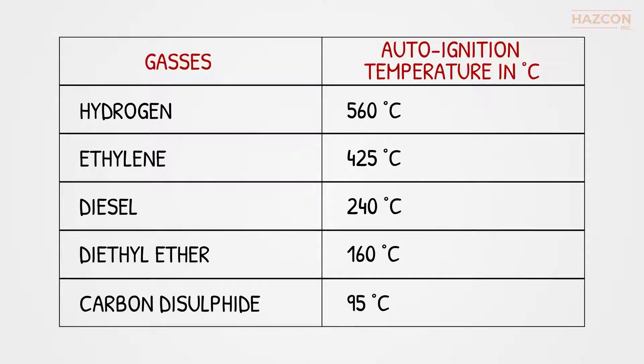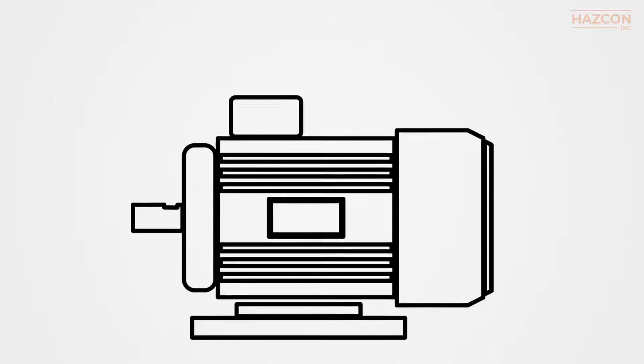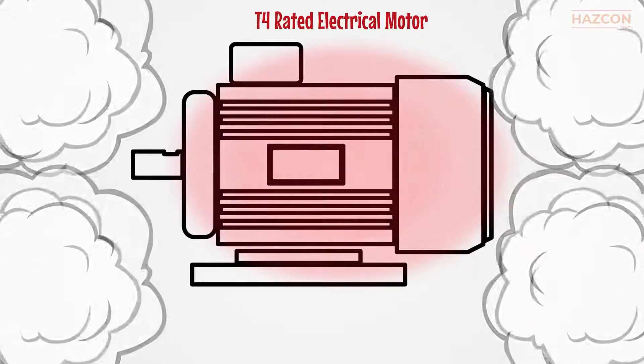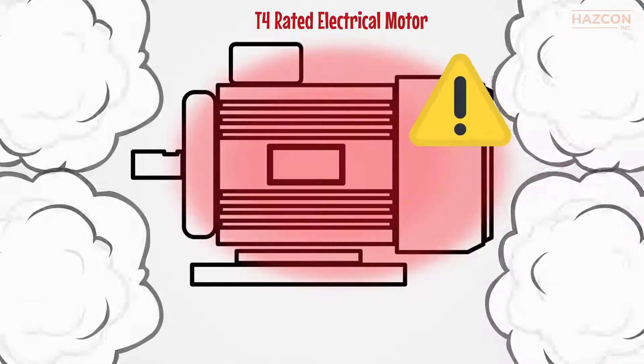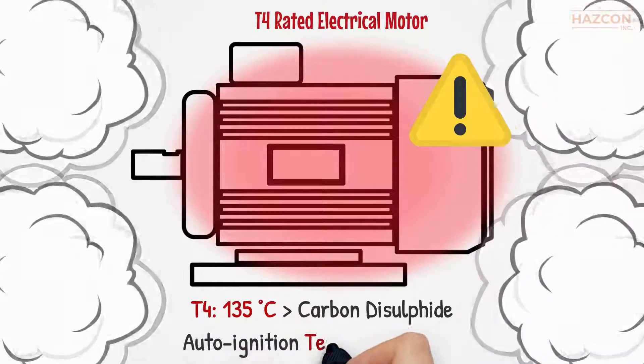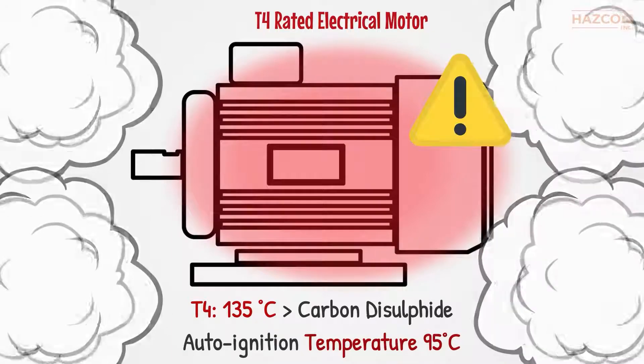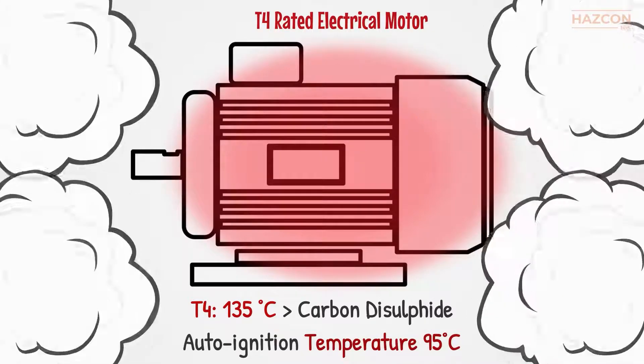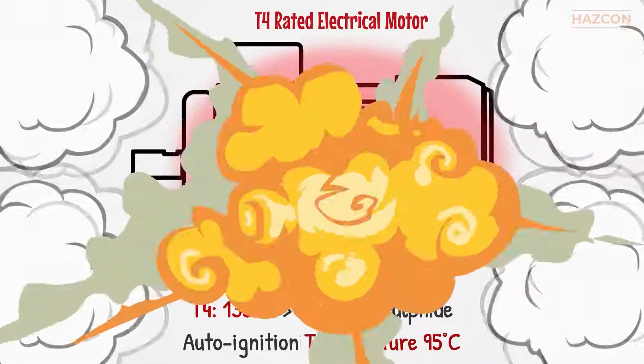Let's use an example to clarify these concepts. We have an electrical motor rated as T4 for installation in a hazardous location. If this motor were installed in a location in which carbon disulfide with an auto-ignition temperature of 95 degrees Celsius is present, the result would be an explosion.